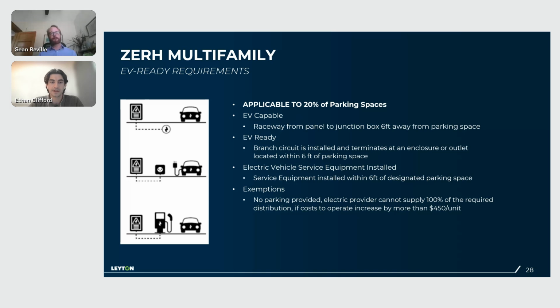Another electrification ready requirement is around electric vehicle ready. At least 20% of your parking spaces for your project should be EV capable, EV ready, or have electric vehicle service equipment installed. EV capable is having a raceway from your panel to, let's say, a junction box, within 6 feet of your parking space. EV ready takes that to the next level, actually having a branch circuit or outlet installed within 6 feet of your parking space. Having electric vehicle service equipment installed means having that charger installed, ready to charge vehicles on site.